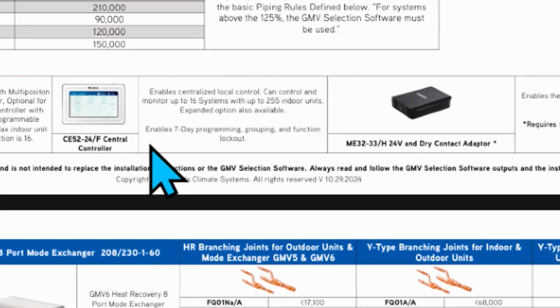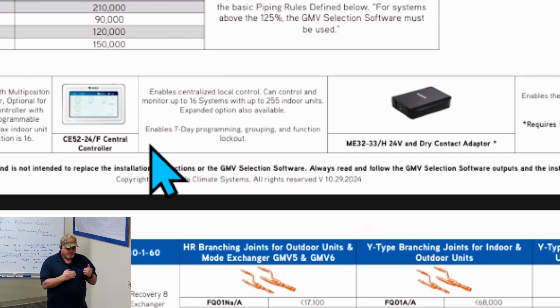When you're doing central control, in other words, you're going to have up to 16 systems. It's very important, whether you're putting in that central control or doing Cool Master, which is coming up next. Both of those use the same protocol to central control or control via the web all of those systems, meaning all the outdoor units and all of the indoors. You have to make sure you set that up ahead of time. You don't have to. We can fix it, but it's more painstaking on the person installing it to get it back to where it needs to be.